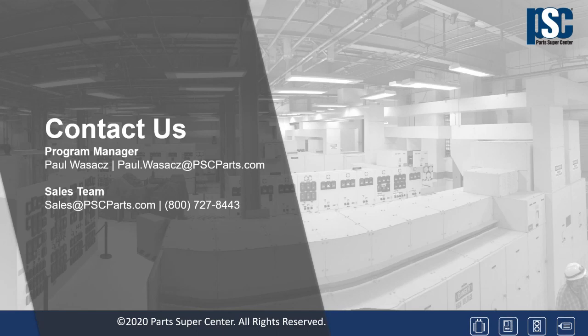Perfect. Thanks, Paul. The next question is, is there a master list available that would show all service advisories recommended by breaker model number and or age? There is not a single list that has all of the service advisories for all the breakers and all vintages and ages and ratings. However, that granddaddy of SALs that I mentioned earlier does have the majority of the modern service advisory letters listed on it, and the most important ones.